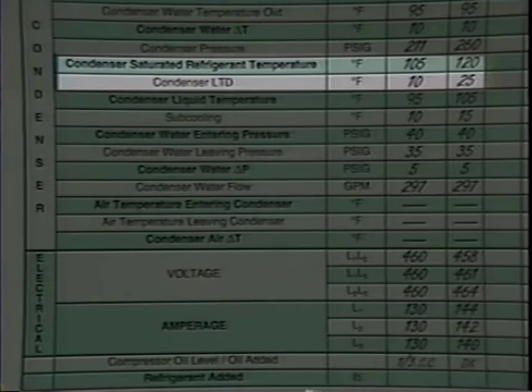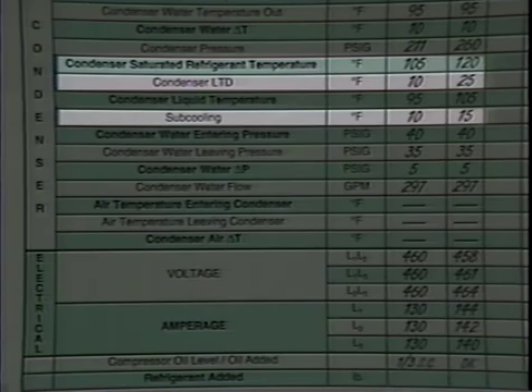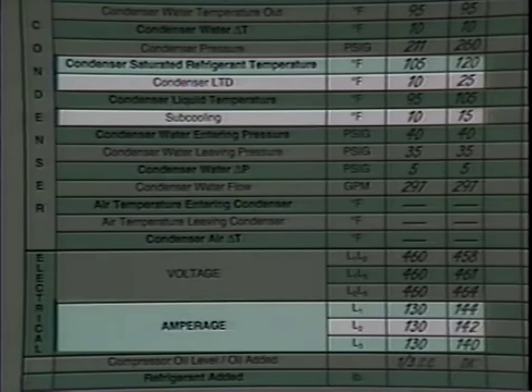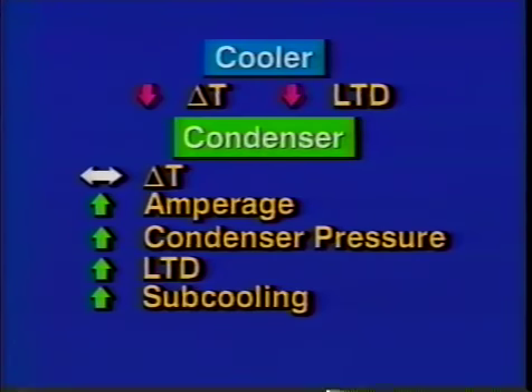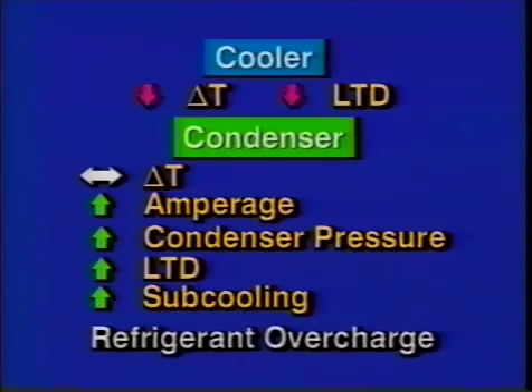Taking a closer look at the condenser data, we will see that the subcooling has increased from 10 to 15 degrees. Also, if we look at the chiller's amperage data, we will see that it too has increased. So, if we summarize the data trends in this situation, we find the chilled water delta T and the cooler LTD are less than design conditions, indicating the cooler capacity is low with no apparent resistance to heat transfer. The condenser delta T is at or near design conditions with chiller amperage, condenser pressure, LTD, and subcooling higher than design conditions. We can therefore conclude the problem is refrigerant overcharge.